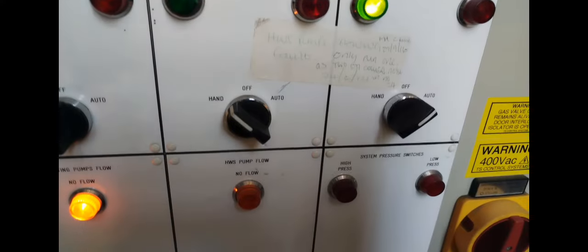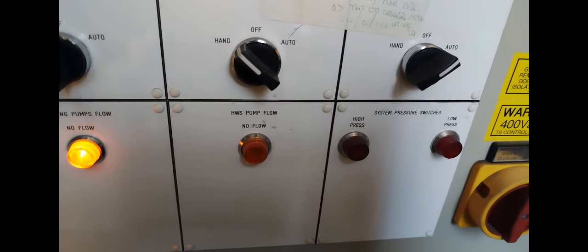This is another site, another visit of a site. Just inspecting pipe work, looking for faults on pumps. Sometimes the indicator lamps don't all work. You can do a lamp test. Yet the last time I did carry out a lamp test, I recall a BMS panel shutting right down. And then I was asked, why did you test it? I did manage to reinstate it, but just be careful when you hit the lamp indicator test button. It can sometimes cause problems.